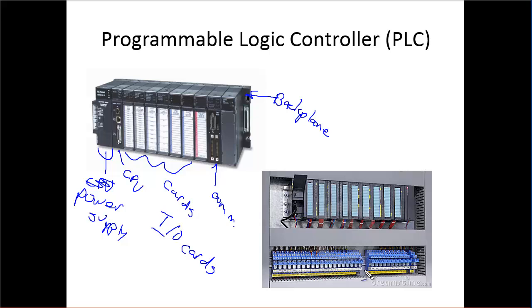So here's the PLC in the cabinet. And then these down here are called terminal blocks or TBs. And so typically what will happen is you put your TBs in here and you'll wire from the TB up into the PLC, make it all nice and neat. And then out down on the bottom of the TBs, you'll have all your wiring going to your instruments and your devices out in the field. And then this right here is called Panduit. And it's actually kind of neat, but it's just to kind of hide the wires and make it all look neat so that you don't just have a jumble of wires when you open up a cabinet. Keeps you from snagging the wires and stuff when you're working in there. Not only makes it look nicer, but it's functional. So this Panduit stuff, the cover just pops off right here and then you can see all the wires in there. And then on the side it's got these little fingers so you can feed the wires out through it.